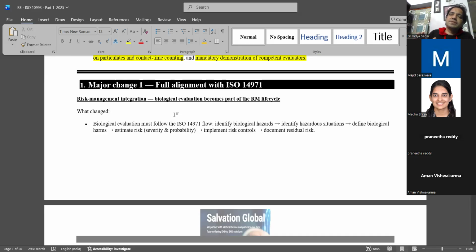have a separate section to write. I'll share the BEP with you. In your biological evaluation plan, you need to write what your decision-making tree or flow for biocompatibility studies is. For everything you need to give a justification. Why you have done this is fine, you can give the justification. And why you have omitted others, you also need to give a justification, which was not there earlier.